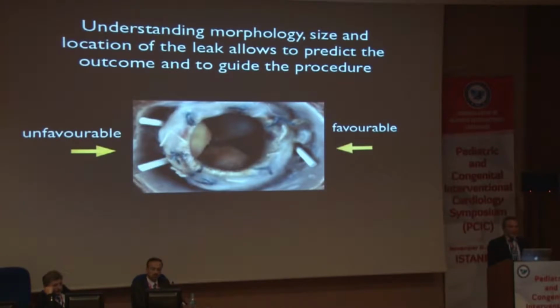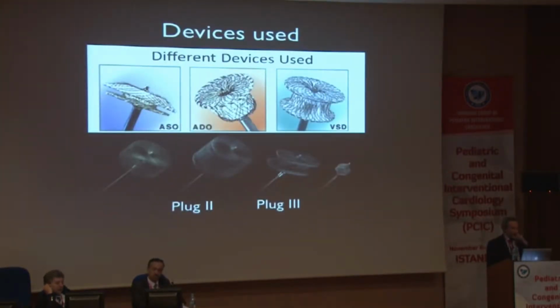We have to understand exactly the morphology, the size, and the impact of the leak. Sometimes it can be favorable, in the sense that it is relatively small and rather rounded. Sometimes it is large and crescentic in shape, and is more difficult to close. There are several devices that have been used for closing paravalvular leaks, like ASD devices, duct devices, VSD devices, or plugs.